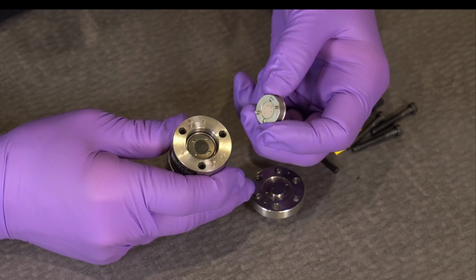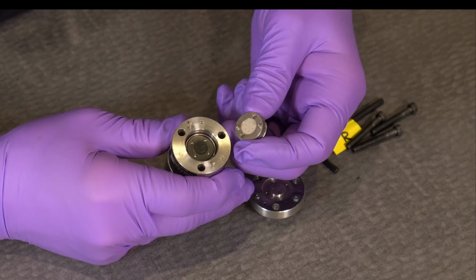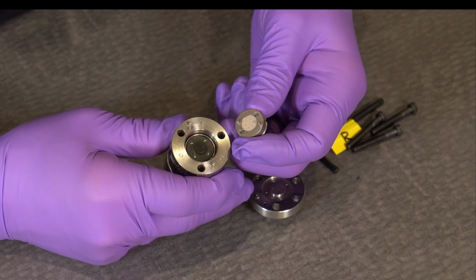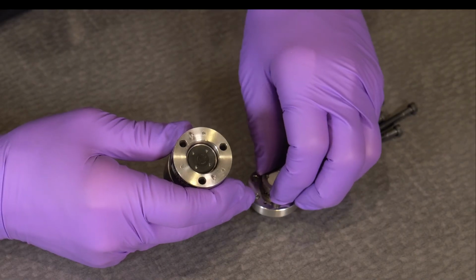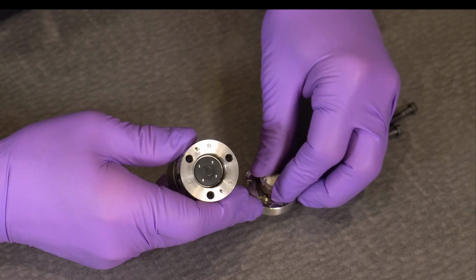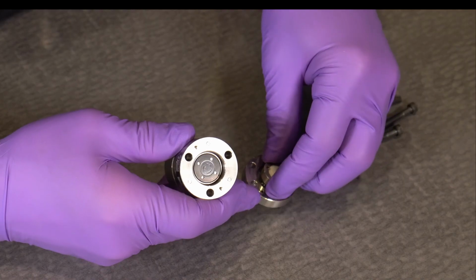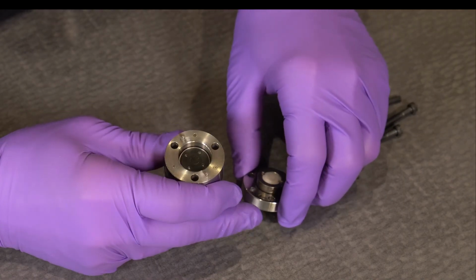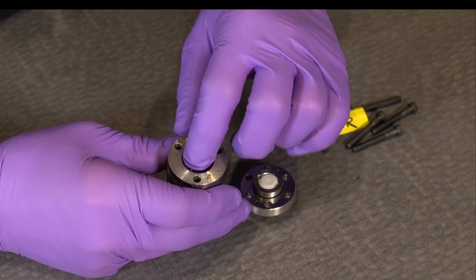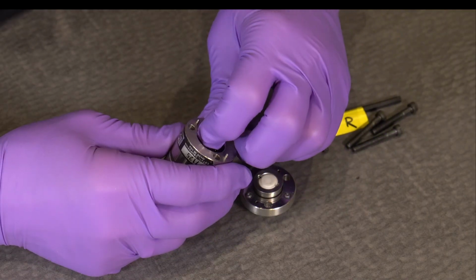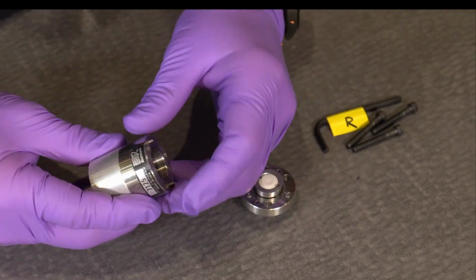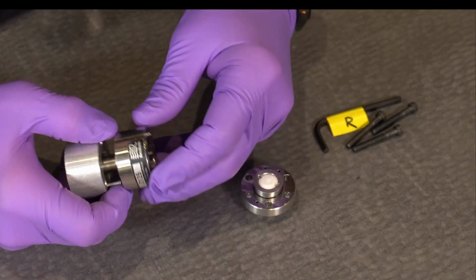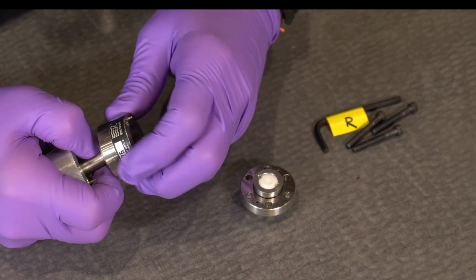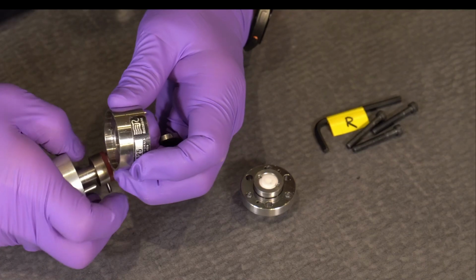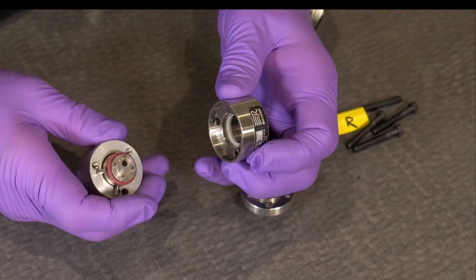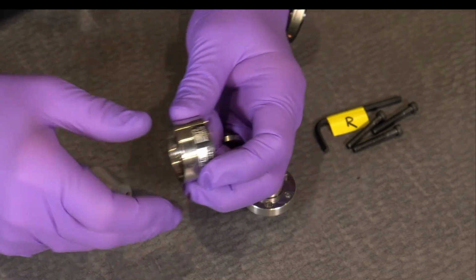Remember I said this can only go back together one way. You see the back of the stator, those 2 little pegs? Those fit in these 2 little holes, and that aligns everything. So it's more tedious than it is difficult. The next part is we're going to remove that seal. You can pull this whole part out. This part remains inside the instrument, so you don't have to worry about that.